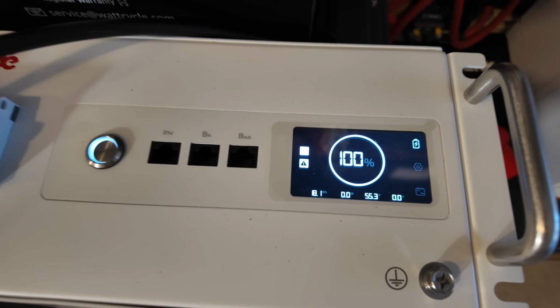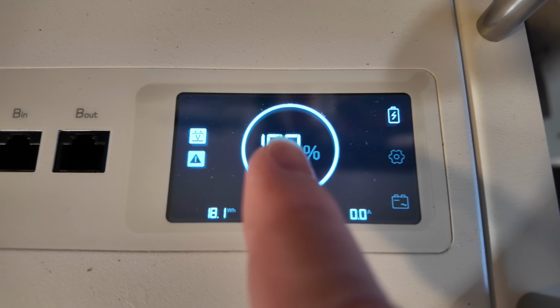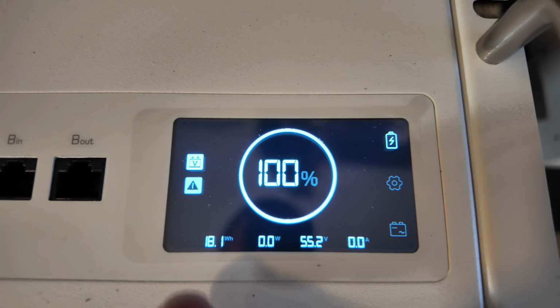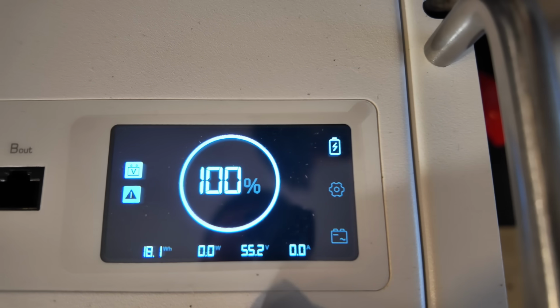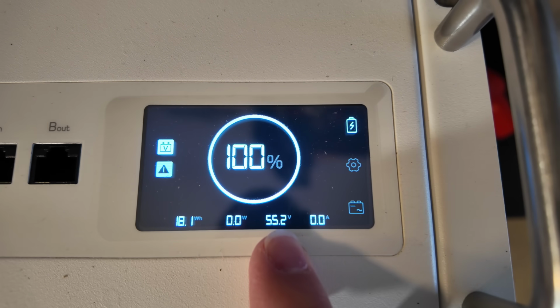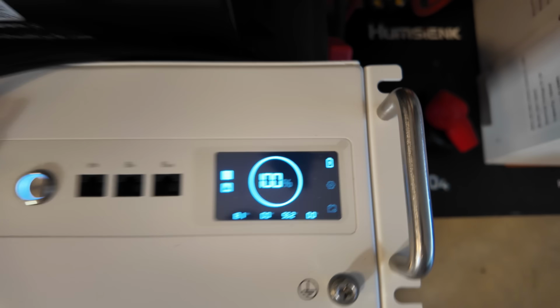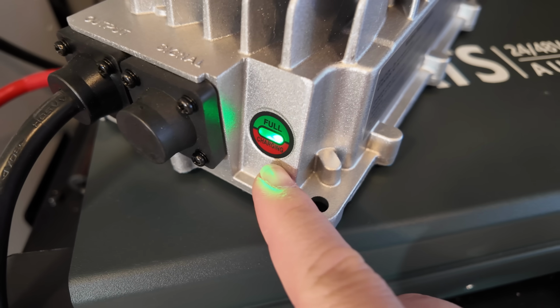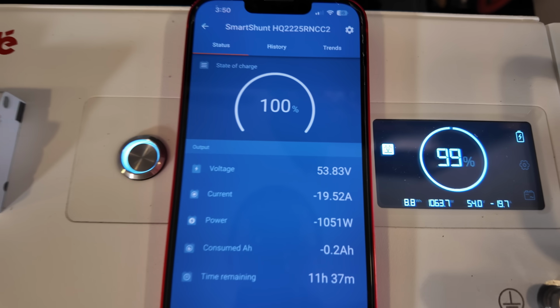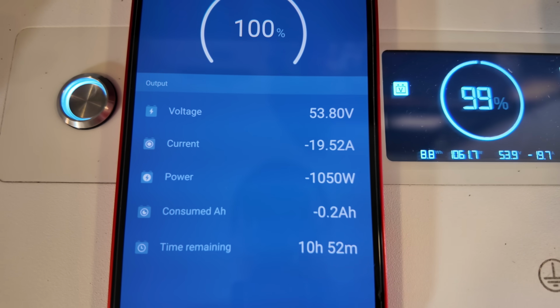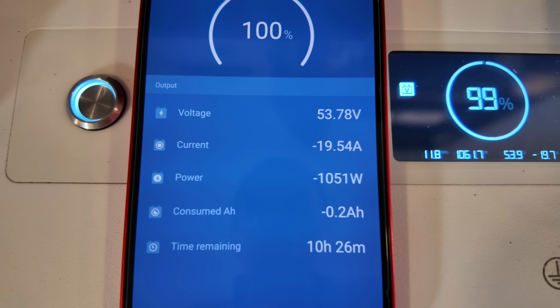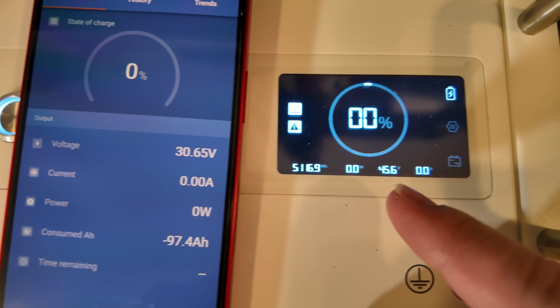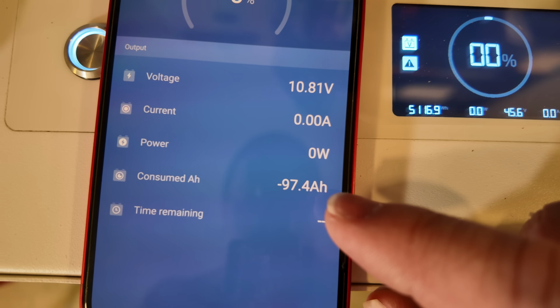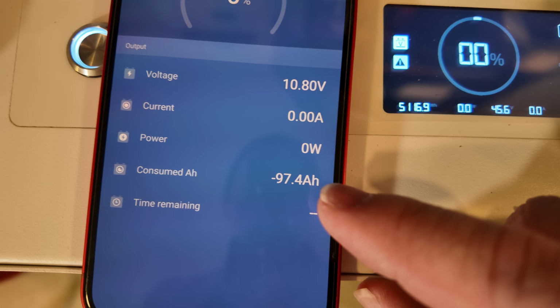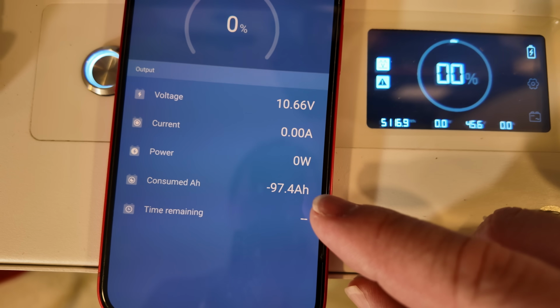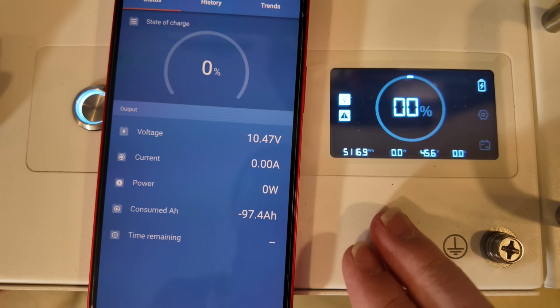Okay, take 2 on this battery capacity test. You can see we're at 100% state of charge. We actually have an overvoltage protection warning because it just barely finished charging. You can see we're still sitting at 55 plus volts. Our battery charger has a steady green light. Second battery capacity test on its way. You can see we're pulling really close to a 0.2C rate of discharge. Okay, it just barely clicked off. And you can see we're dropping our voltage, but 97.4 amp hours. So quite a bit closer than the first time.